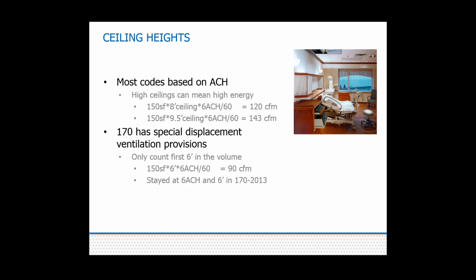So it can affect your energy use. Also in a new facility, if you choose to do displacement ventilation, Standard 170 only counts the 6 feet of the height into the volume, which could lower you in this case to 90 CFM. Do note, however, that stayed at 6 air changes and 6 foot in height in the 2013 version. So actually with an 8-foot ceiling and 4 air changes, if you're on the newest version of the code, you'd actually get a little below that, down to 80 CFM. I've never quite understood why these are done on an air change basis. To me, having a taller ceiling doesn't add contamination to the room. I'd prefer some of these things be done on a square foot basis, but I don't write all the codes. So next slide, please.